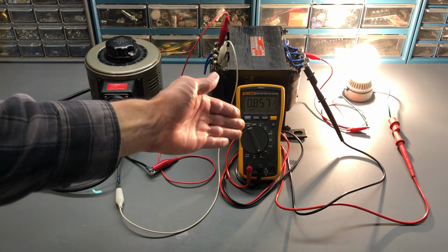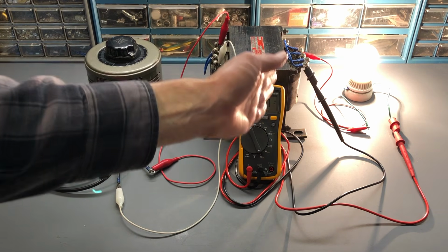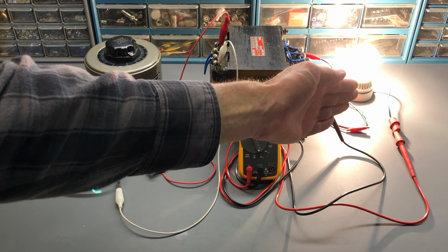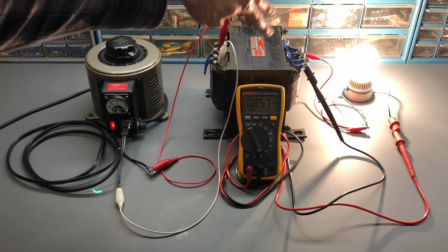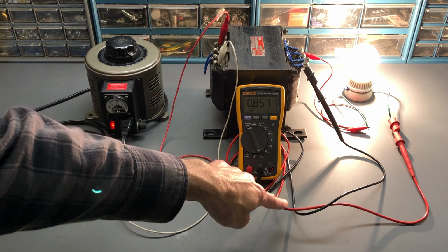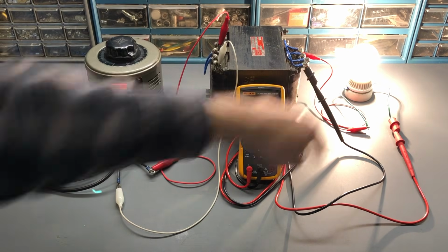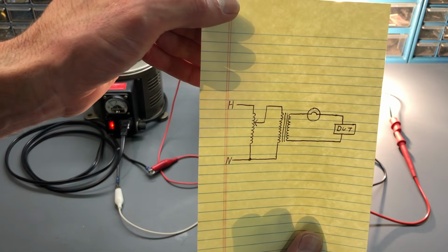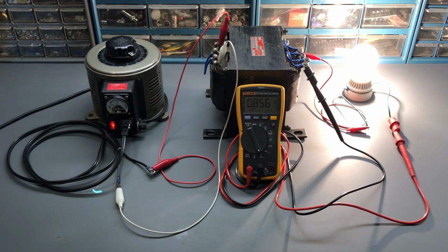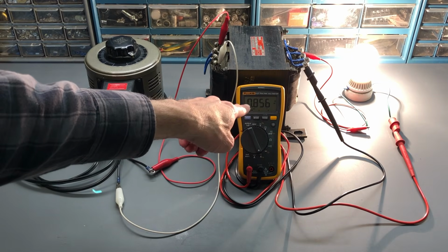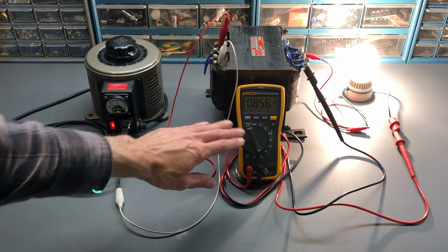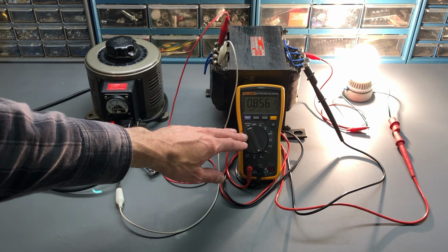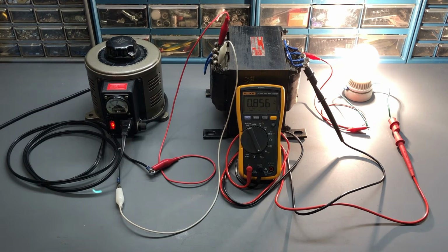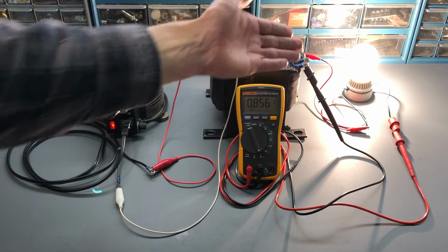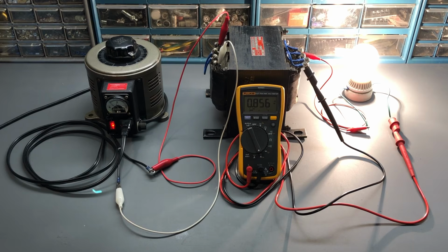So with a direct short being applied, basically on the other side of the incandescent lamp, because again this is now not across the secondary windings. One side of this amp meter is connected to the incandescent bulb. All right, move that bulb over to the other side of the transformer for this setup, and you can see the current flow through the meter, 0.856. Again, this meter would be simulating the device that we would be testing. So if the device failed and had a direct short, we'd be limited to 0.856 amps with a 100-watt bulb. A larger bulb would allow more current to flow. A smaller bulb, you'd have less current flow.